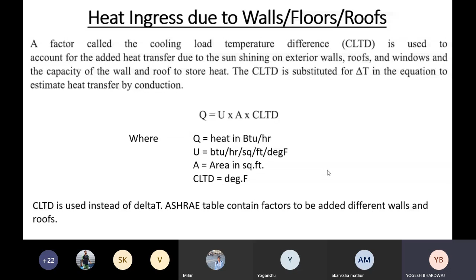floors, and roofs. Then heat ingress through glass. So through glass, like I told you, heat will come in two ways. One way is the conduction heat gain, like it is coming from wall. Similarly, it will also come from roof. That depends upon the U value of glass, the area, and then CLTD. The another heat gain is the radiational heat gain. So radiation heat gain can be calculated by multiplying the area into shading coefficient and into solar cooling load factor.